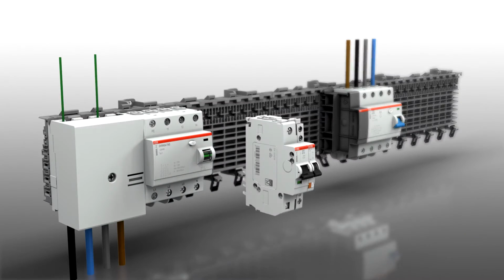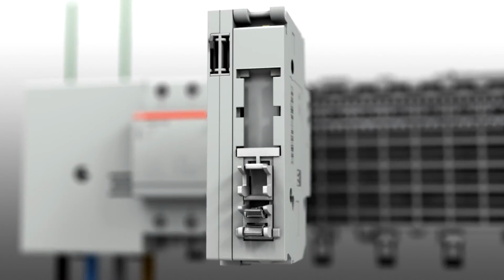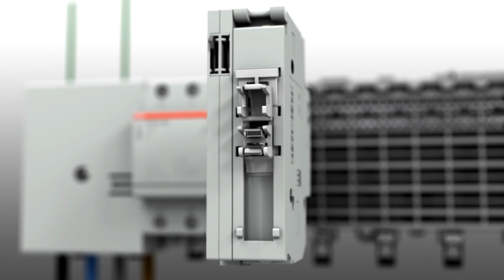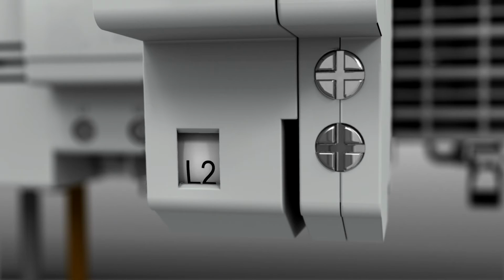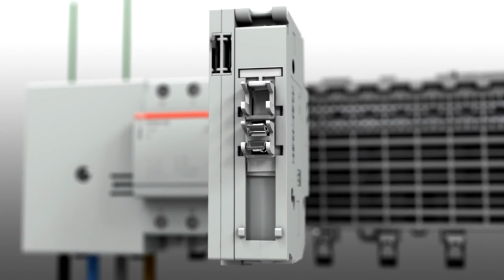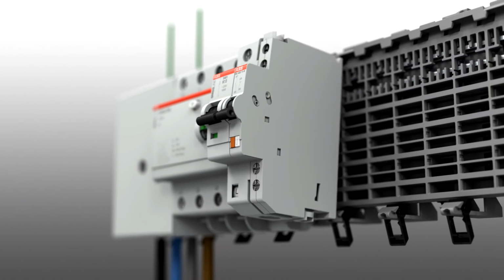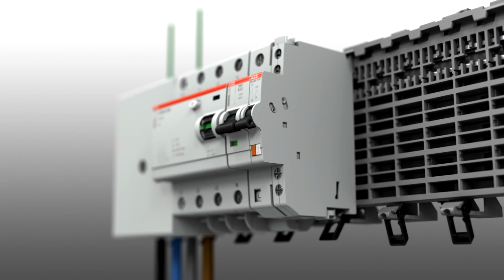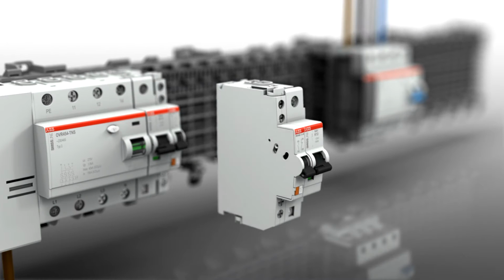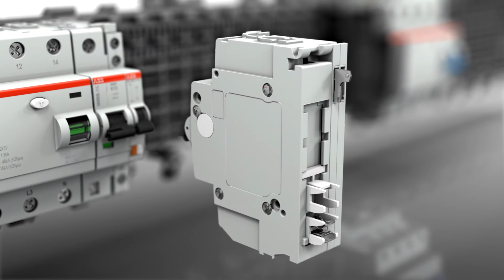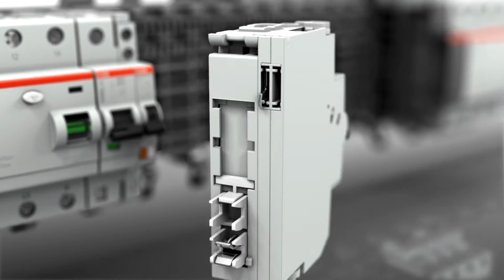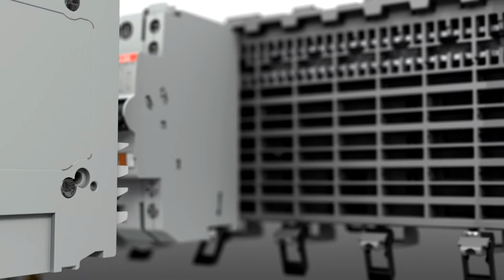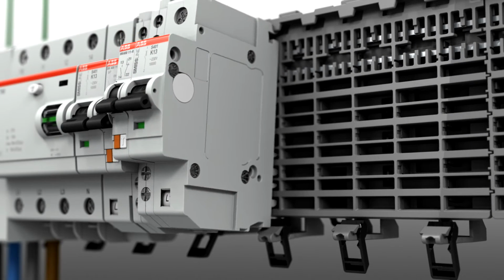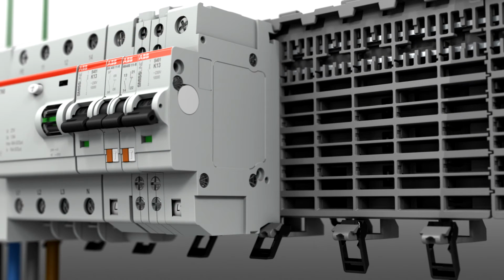To prevent unsymmetrical loads, the contact arrangement of the external conductors can be changed by simply moving the plug contact. The pole conductor contact arrangement can be identified without removing the devices. Even the signal and auxiliary contacts can be supplied with power directly. This obviates the need for input wiring. A collective alarm message can be output directly via the two auxiliary bus bars integrated in the socket, for example.